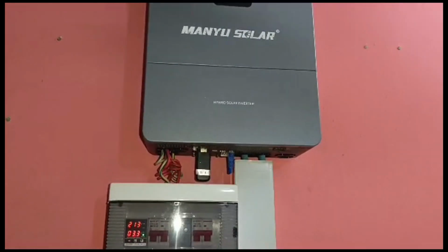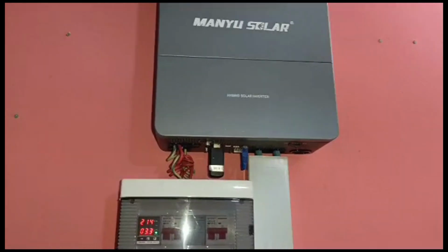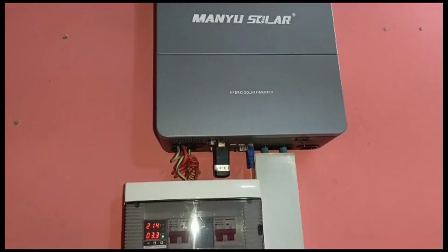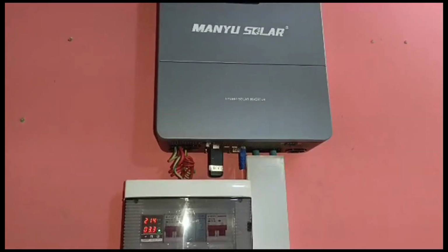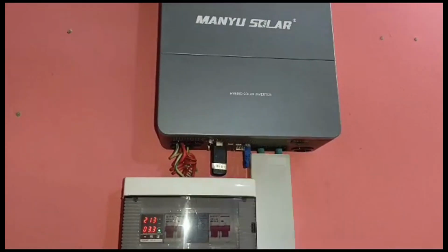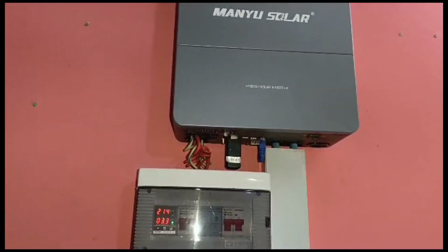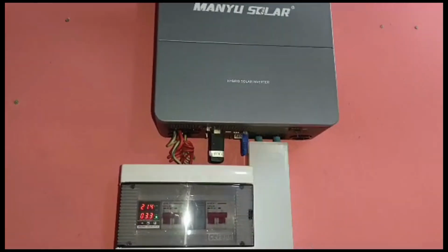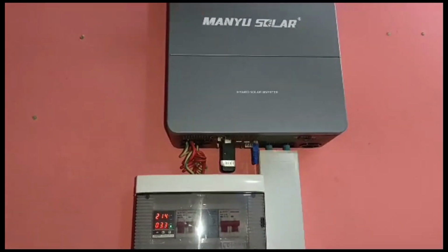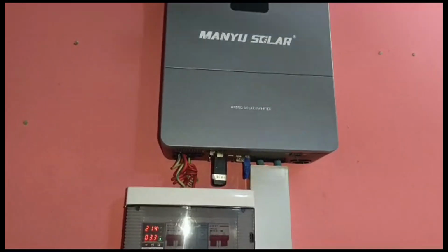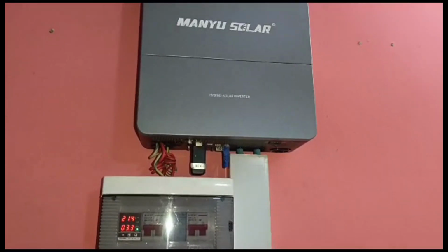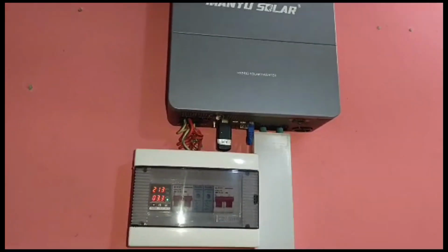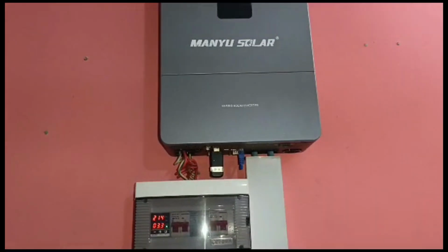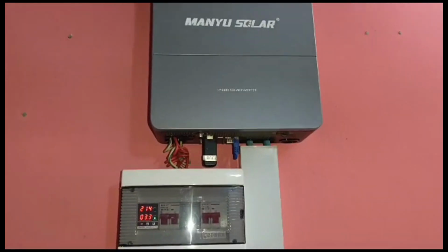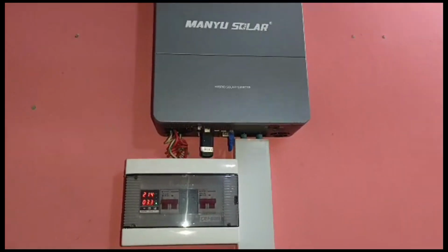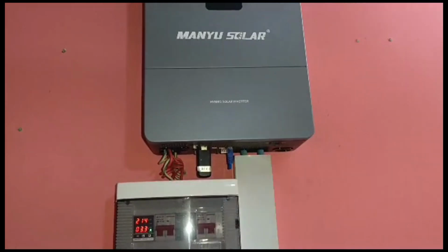And you have other loads in the kitchen which are not connected to the inverter at all, although there is a socket there in case of an emergency, maybe they need to use the blender and there's no light and we can't wait, so we can actually do that. The inverter can support that. So everything is all about the bucket, the battery. The inverter is 5 kilowatts, so it can support all those loads, but the bucket is the most important in this case. The stored energy, the battery.